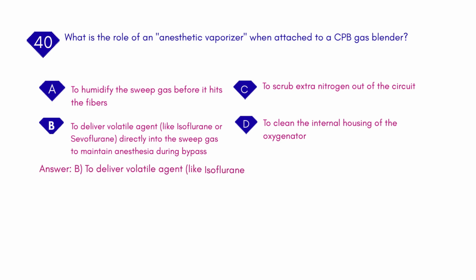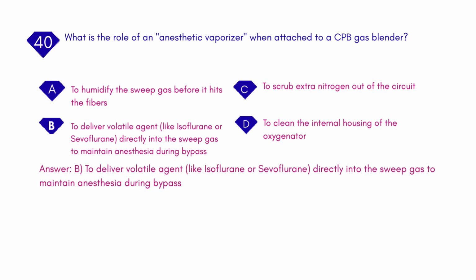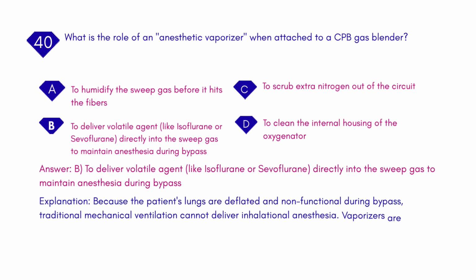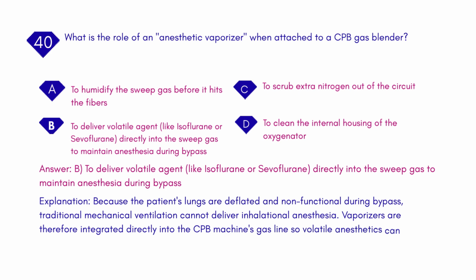Answer: B. To deliver volatile agent, like isoflurane or sevoflurane, directly into the sweep gas to maintain anesthesia during bypass. Explanation: because the patient's lungs are deflated and non-functional during bypass, traditional mechanical ventilation cannot deliver inhalational anesthesia.